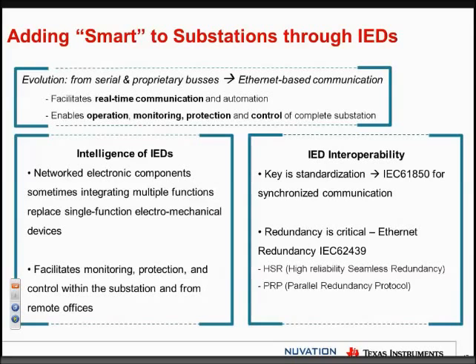What do we mean by adding smarts through intelligent electronic devices? Communication has transitioned from what used to be a traditional serial or proprietary bus to more Ethernet-based communication. This enables real-time communication of the automation functions, enabling operation, monitoring, protection, and overall control of the complete substation.